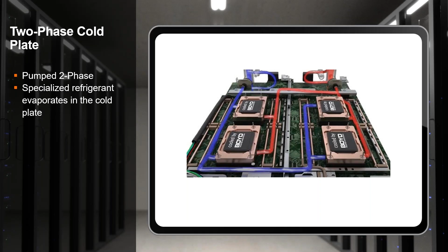Let's talk for the last few minutes about 2-phase cold plates. You're probably familiar with 2-phase heating or cooling, the idea that we change phase as a way to move heat from one place to another. We're using the latent heat of phase change instead of a change in temperature. These are usually pumped refrigerant systems, not like an air conditioning unit with a compressor. We're using a specialized refrigerant that goes into these cold plates and actually vaporizes inside, pulling the heat out.